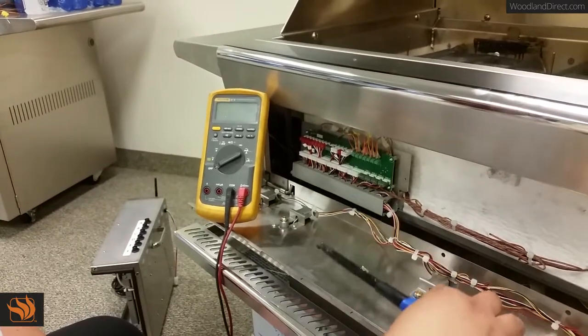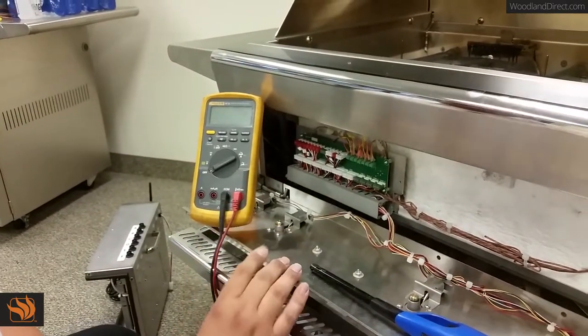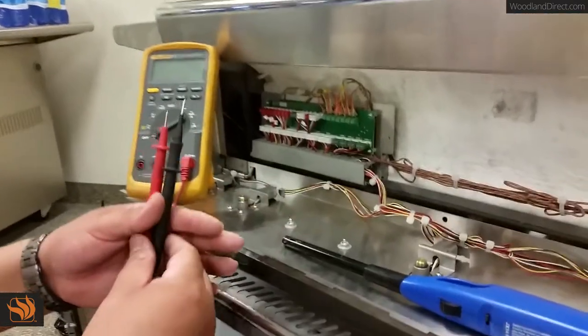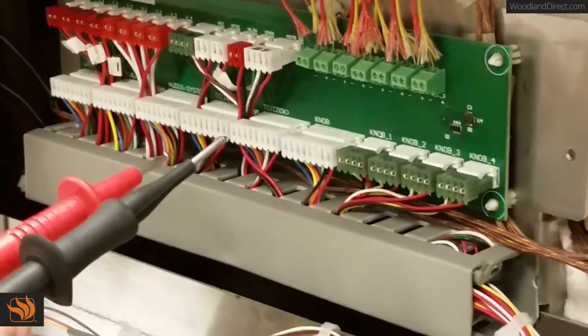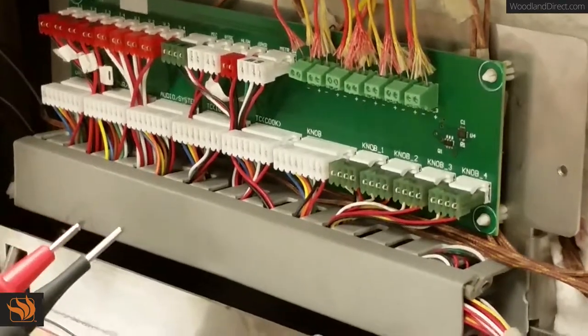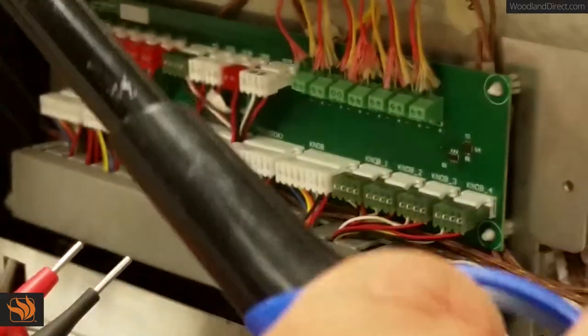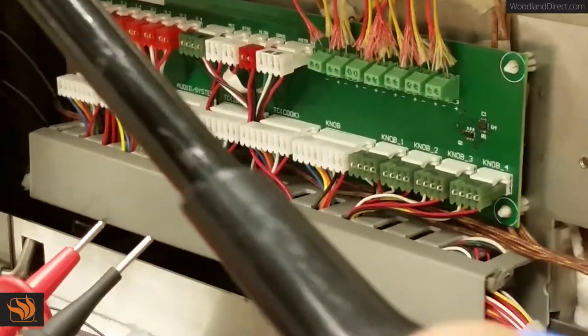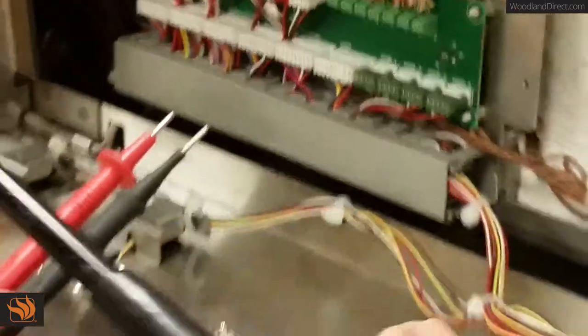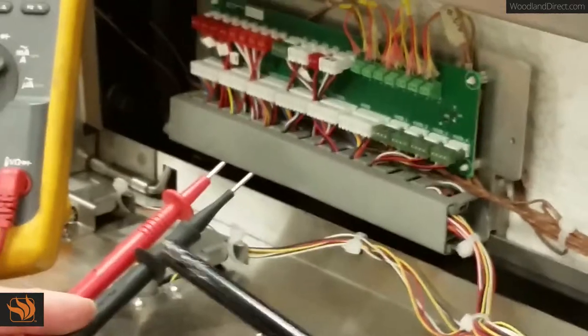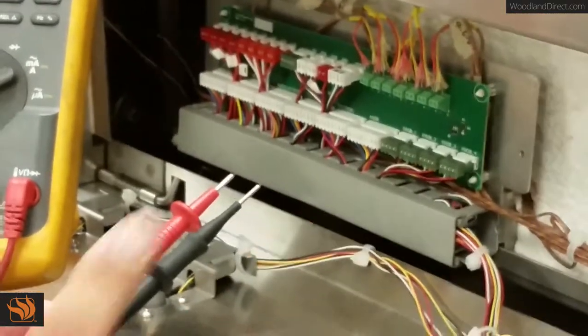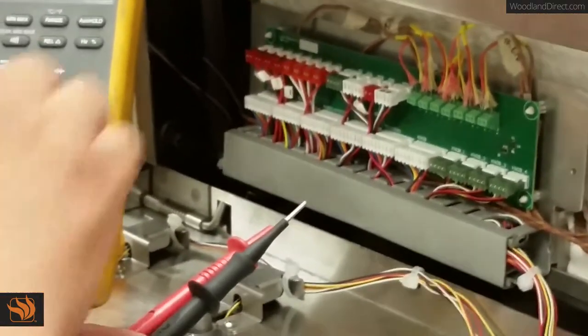In this case we have just a little butane lighter. What you want to do is use the probes on the multimeter according to the polarity and fire up the source of heat and apply the heat to the individual TC to make sure that it's functioning. You will see a climb in temperature if the TC is working properly. So I'll show you how to do this one here.